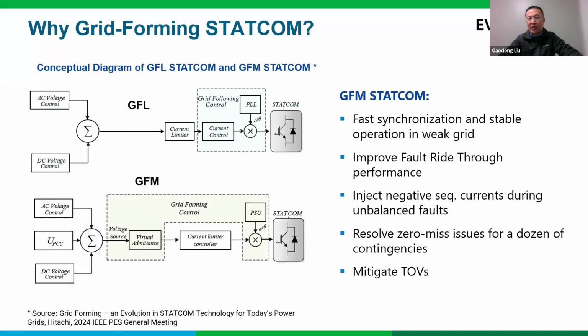We know that the STATCOM can be installed with different controls. The conceptual diagram here, the grid following STATCOM and the grid forming STATCOM, I think is pretty well known. So the grid forming control strategy STATCOM is that the converter behaves like a voltage source behind an impedance. One thing important to note is that the STATCOM synchronizes with the grid based on the active power mismatch between the STATCOM and grid. So this is the behavior of the grid forming STATCOM.